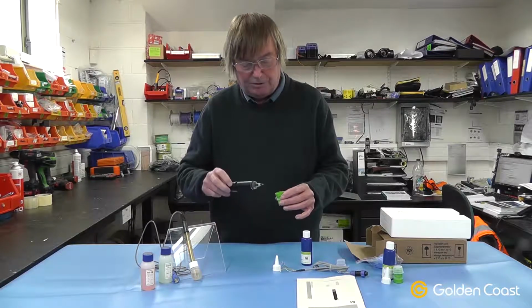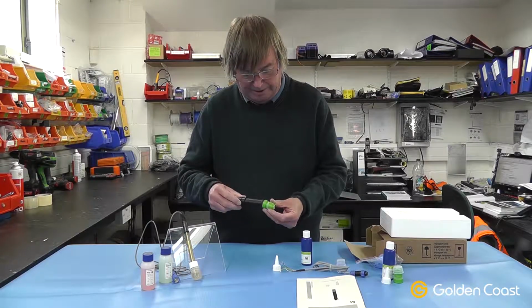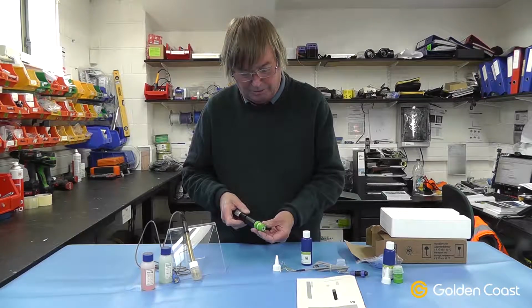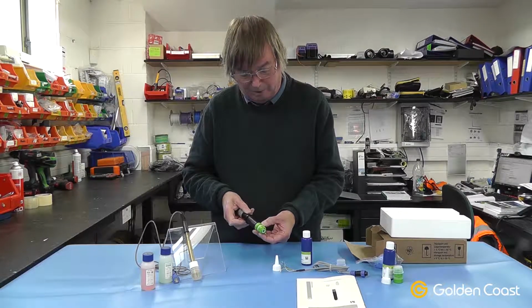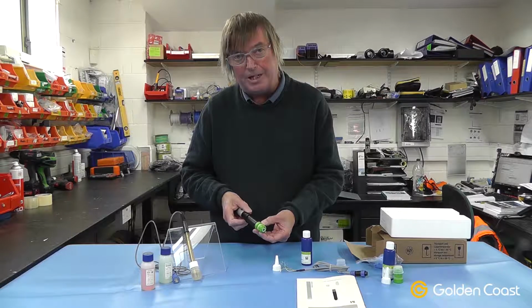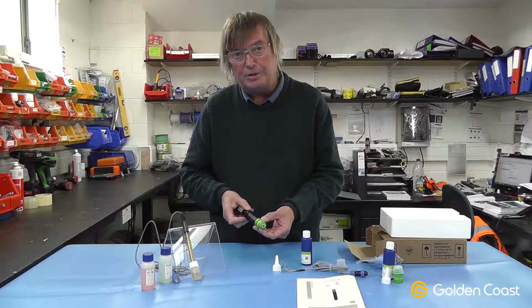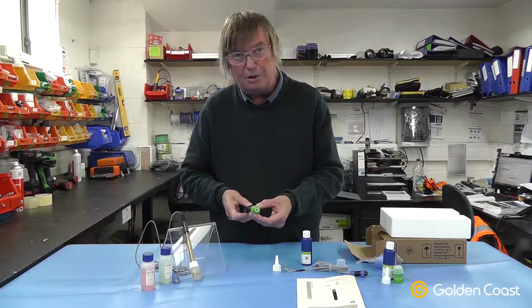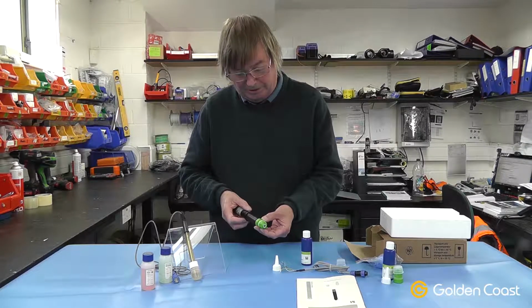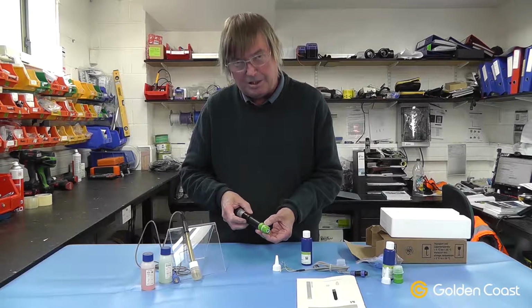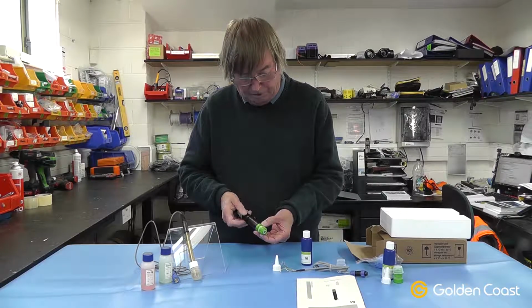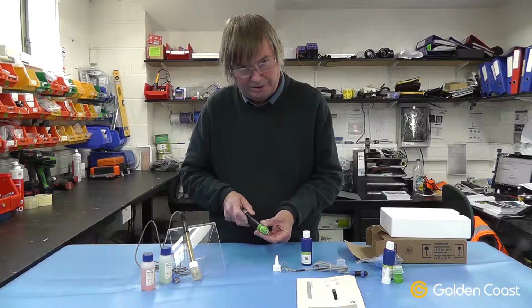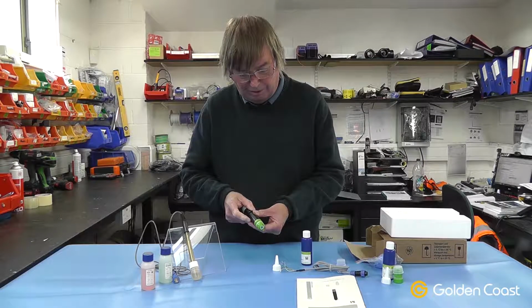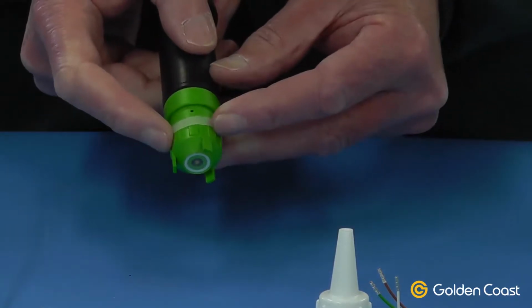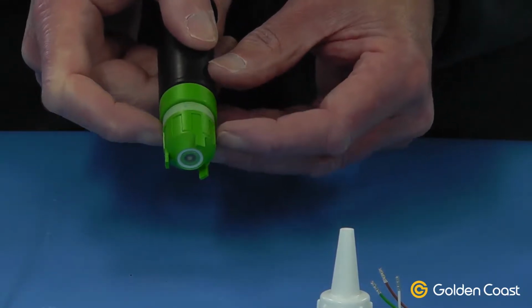The reverse procedure, of course, is you screw the cap back on, and when you're screwing this cap on, you will see the excess gel come out of the weep hole. This operation of screwing the cap on should take 5 minutes. If you do it any quicker, you're doing it too quick, and you could again blow a hole in that membrane cap. So you have to do it very slowly, letting the excess come out of that weep hole. Once you get to the end of the seal, you can feel it's tight and locked home firmly. Then you pull the silicone band back over to cover the weep hole up.